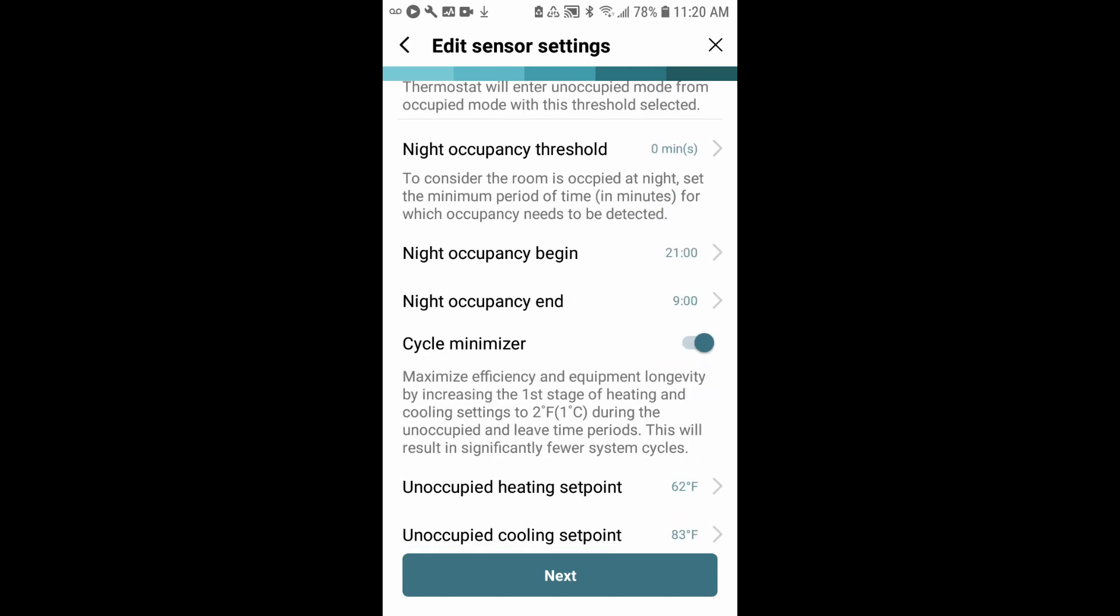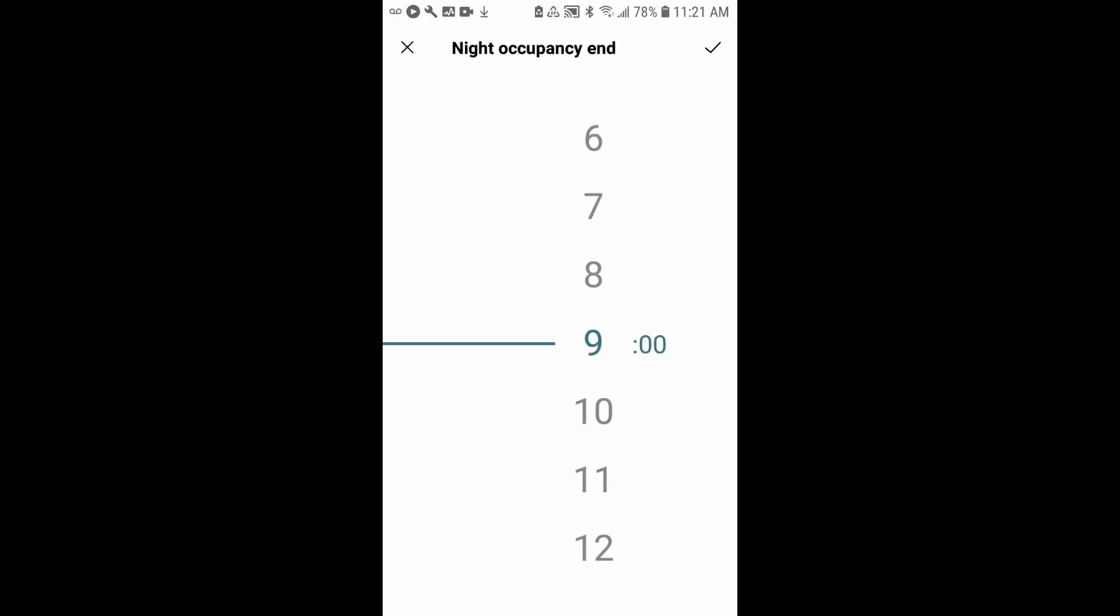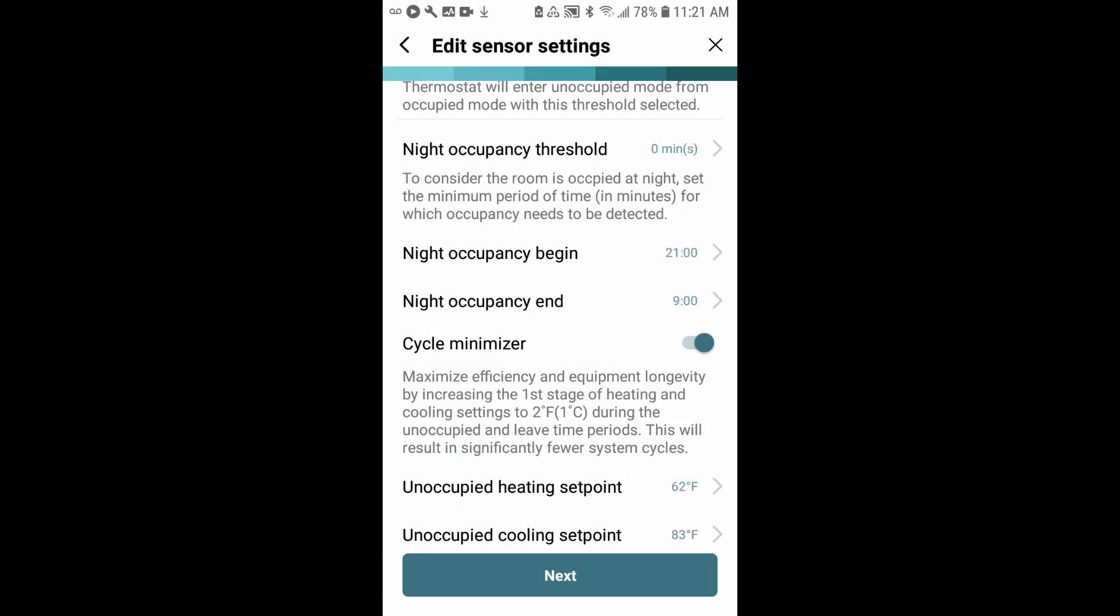And then for night occupancy. This is the time frame in which the system, if it detects occupancy at a certain time in the evening, it will consider the room occupied overnight. It will hold that temperature throughout the night so that when people get under the covers, bundle up, the PIR sensor maybe can't see them or can't detect their body heat. We'll want to hold that temperature overnight to prevent them from becoming uncomfortable. So the night occupancy threshold, again, we set that to zero minutes. At 2100 hours or 9 p.m., if there's any body heat detected, it will instantly go into occupied mode. And it will hold that until 9 a.m. Night occupancy begins at 2100 and ends at 9 a.m. If you would like, you can adjust that there in the settings.